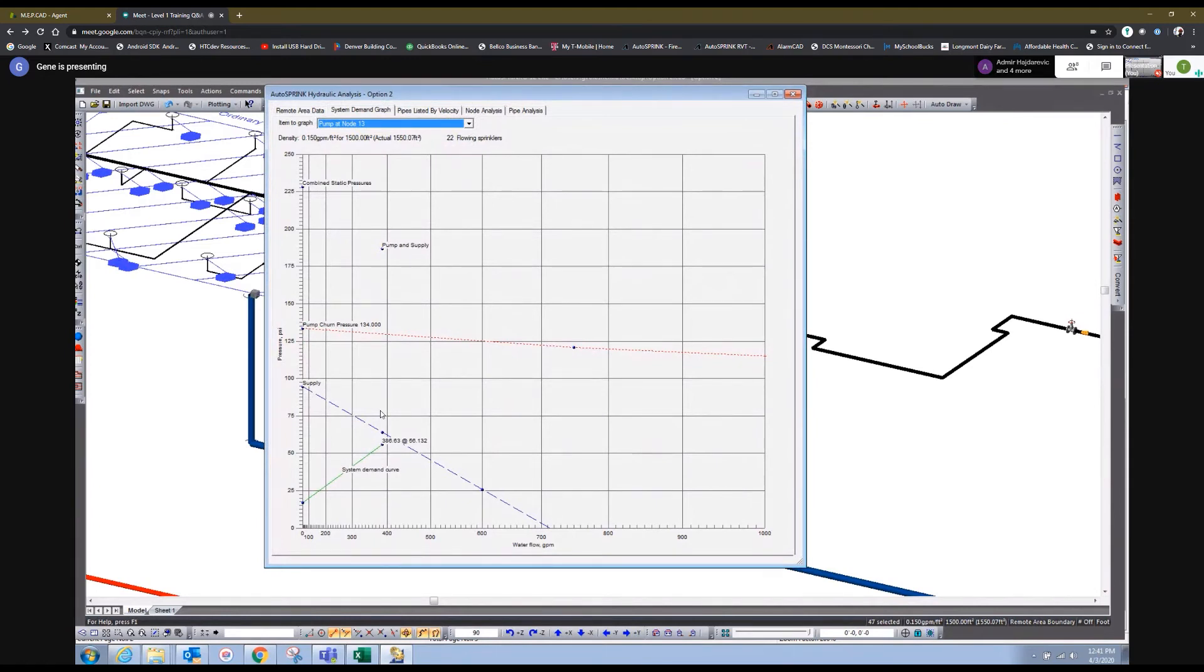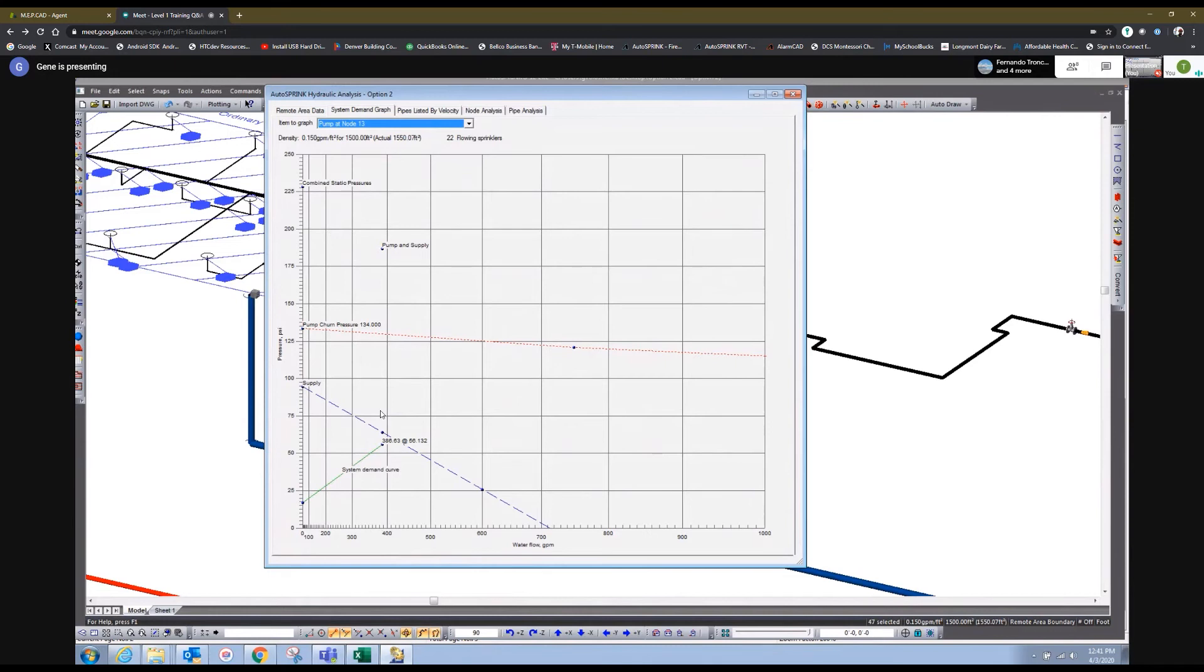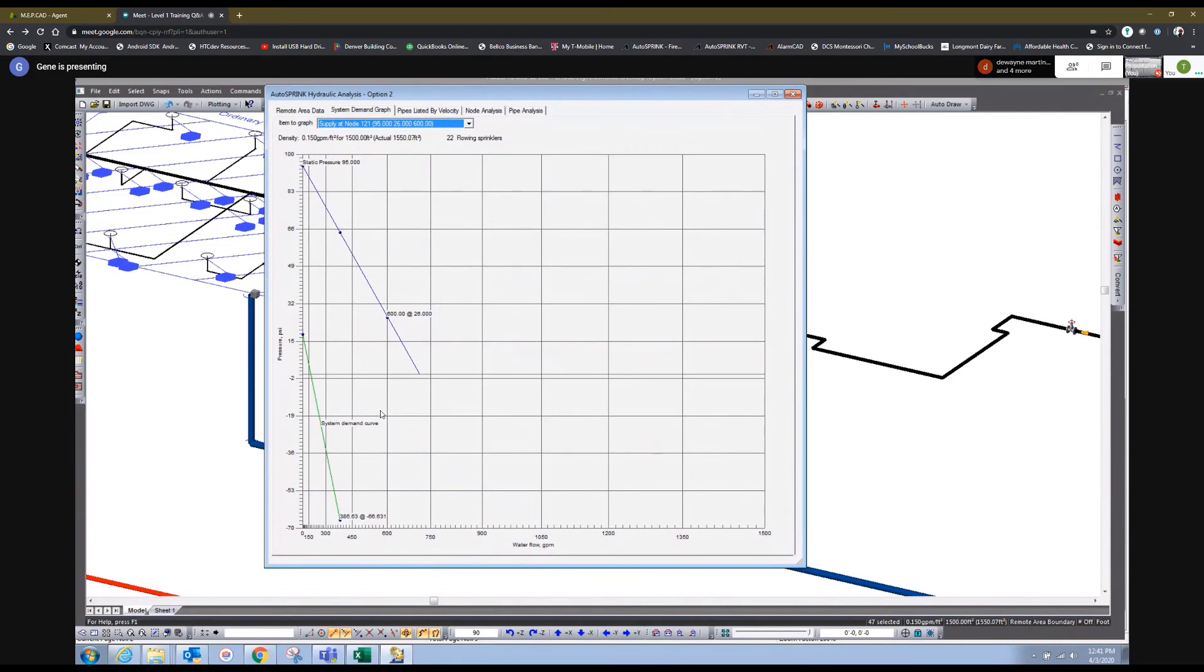Yeah. So, the system demand at the discharge side of your pump is 56 PSI. The pump is gonna knock that pressure down based on your curve that you've established. So, at this flow rate, it looks like your pump is putting out 120 PSI or something. So, at this point in the hydraulic sequence, the program is gonna take 56 and it's gonna knock 120 PSI off. So, now you, that's where you're getting this negative pressure value. And it continues from that point back to the source. Yeah, it's kinda funky, so it's negative 60. Right there. Yes, sir. Alright. So, but, so essentially, alright, I'll go with that. I'm just gonna consider that 56 is at the pump. Yes, sir. That is correct.